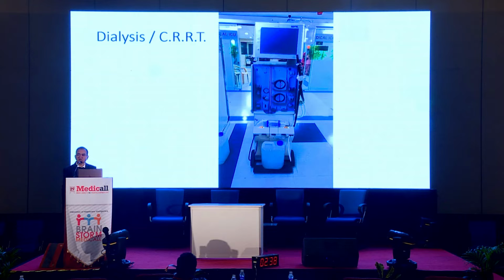One is the offline system, where the RO plant generates RO quality water which is stored in a tank and then fed to the dialysis machine. The second type is the online RO system, where the water is in continuous circulation. This is needed because if there is any stagnant water in the tank or line, there is always a possibility of growth of bacteria, fungus or infection. So to avoid that, online systems are preferred, and in our hospital we have had an online RO system for almost 11 years, with a very low infection rate.